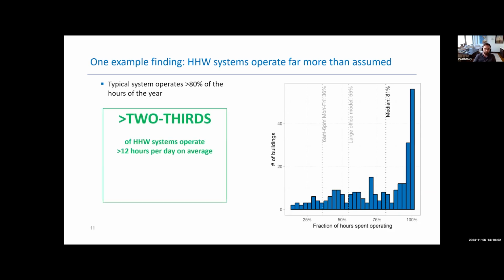Another way of looking at this is two-thirds of the buildings have hot water systems that are operating more than 12 hours per day during the weekend when they're unoccupied, in the summer months when you're trying to cool the building, right? So this is a big problem, right? Or you can look at it as a big opportunity to reduce emissions very cost effectively, because essentially this is just a controls and scheduling fix that almost any automation system can handle. And even in the cases where there are some minor repairs that need to happen to make it feasible to turn that hot water system off, the savings are quite large compared to the cost of that measure, especially when you consider alternative means of capturing savings of that magnitude.